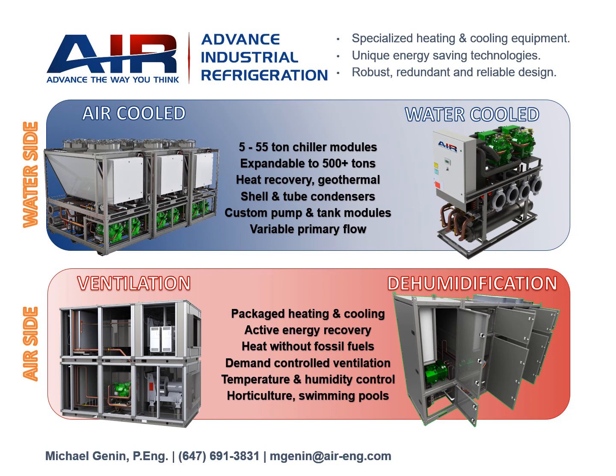What about heating and cooling? Can active heat recovery switch between heating and cooling as needed? Yes, the fresh air unit is equipped with a cooling cycle, and so it can reverse and achieve cooling as needed. And typically you'll have a dead band between heating and cooling, and the controller will automatically make the decision based on the set points that you want to switch between heating and cooling.